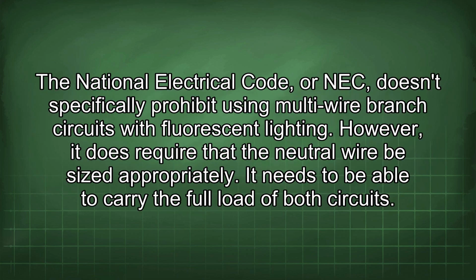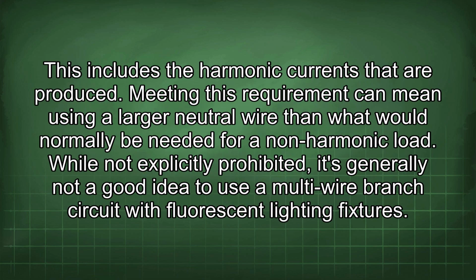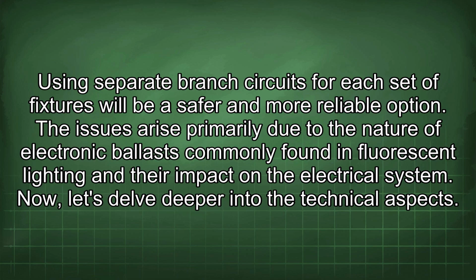The National Electrical Code, or NEC, doesn't specifically prohibit using multi-wire branch circuits with fluorescent lighting. However, it does require that the neutral wire be sized appropriately. It needs to be able to carry the full load of both circuits. This includes the harmonic currents that are produced. Meeting this requirement can mean using a larger neutral wire than what would normally be needed for a non-harmonic load. While not explicitly prohibited, it's generally not a good idea to use a multi-wire branch circuit with fluorescent lighting fixtures. Using separate branch circuits for each set of fixtures will be a safer and more reliable option.